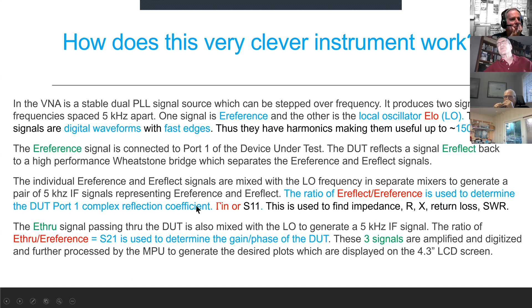The individual E reference and E reflect signals are mixed with the local oscillator frequency in separate mixers to generate a pair of 5 kilohertz IF signals representing E reference and E reflect. And the ratio of E reflect to E reference is used to determine the port 1 complex reflection coefficient, gamma in or S11. This is used to find the impedance, resistance, reactance, return loss, and SWR of port 1. The E through signal passing through the DUT is also mixed with the local oscillator to generate a 5 kilohertz IF signal. The ratio of E through over E reference is S21 and is used to determine the gain and phase of the device under test. These three signals are amplified and digitized and further processed by the microprocessor in the instrument to generate the desired plots, which are displayed on the 4.3-inch screen.